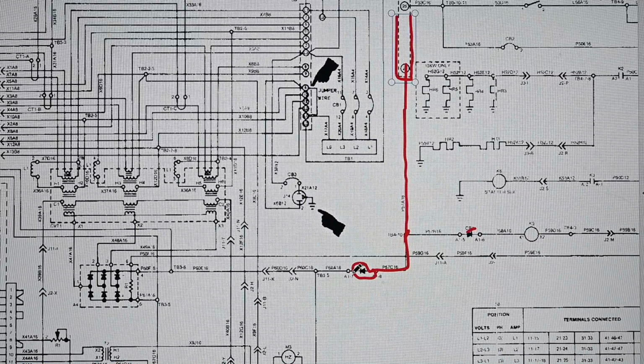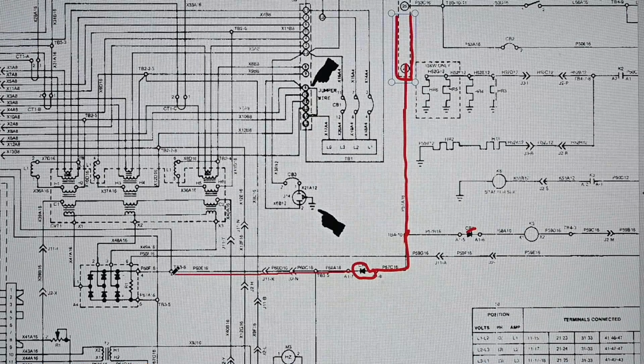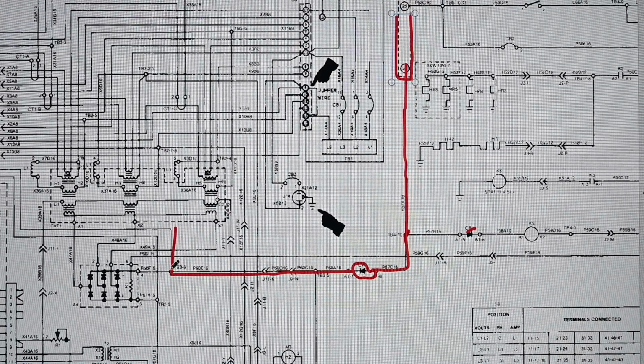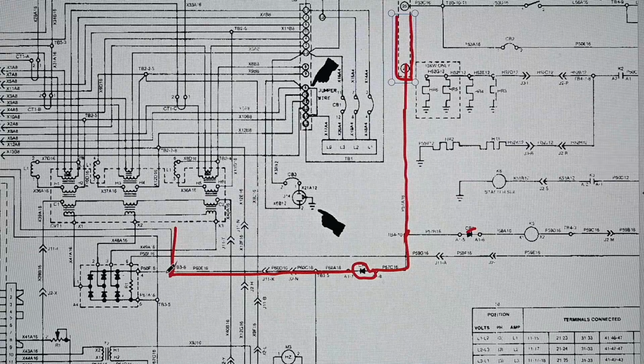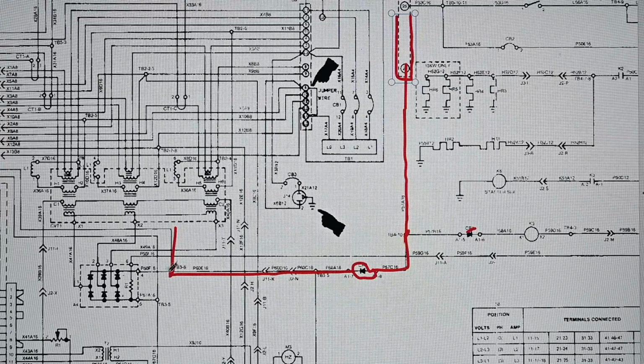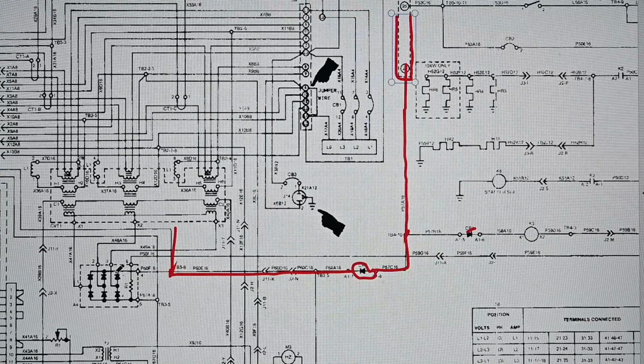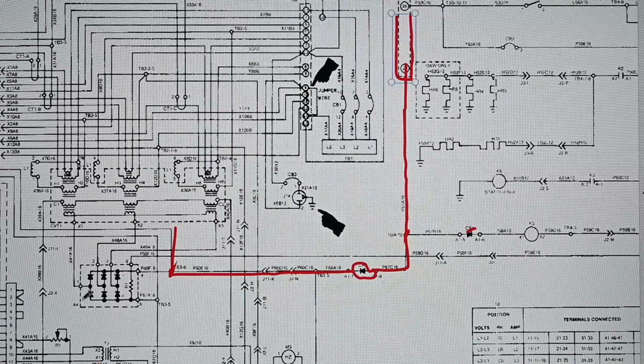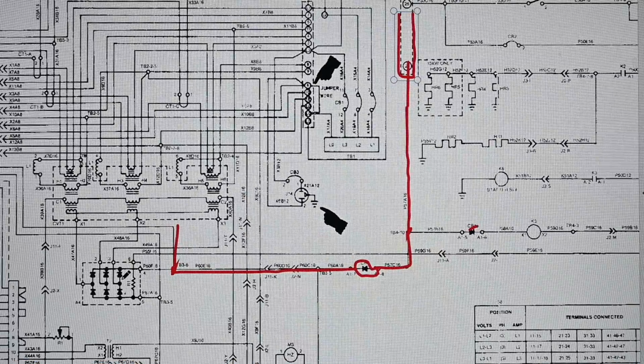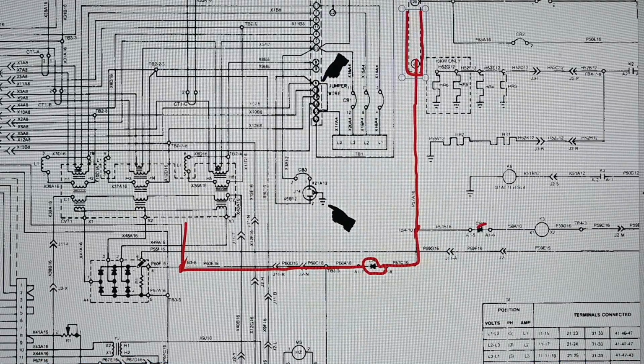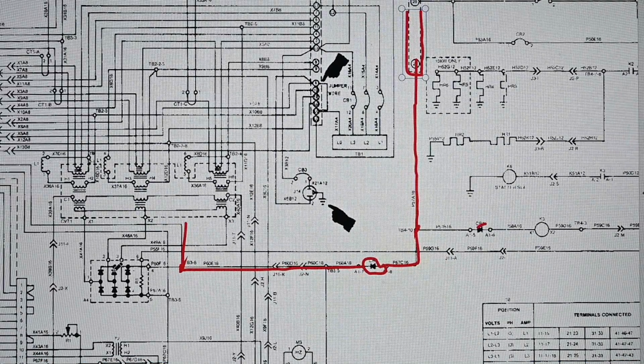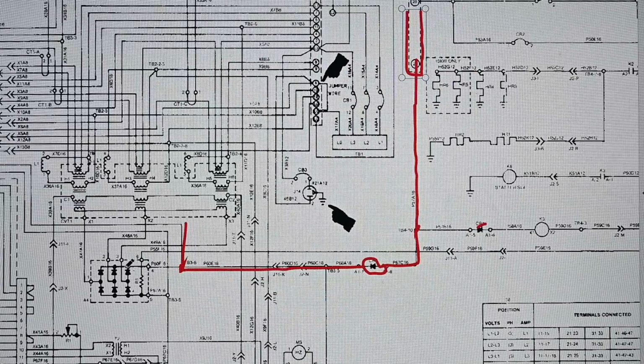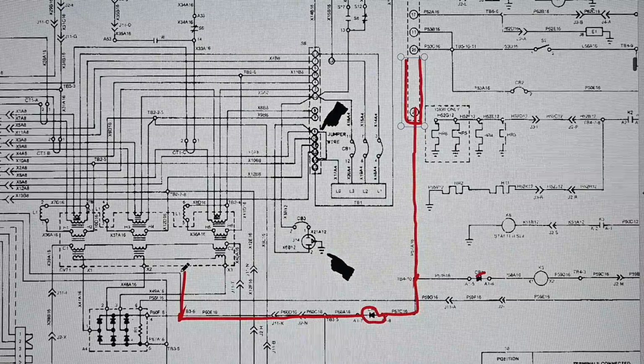So the 24 volts is applied over here, goes all the way across, comes up to this junction. We have a connection, but nothing happens over here. If you follow this path across, we have a diode, another diode, another diode. This is the A4 bridge assembly in that reconnection box. Because you have a positive voltage, that positive voltage does not go through these diodes. This is the negative or cathode side of those diodes, so they block that DC voltage. So the voltage comes up across here.